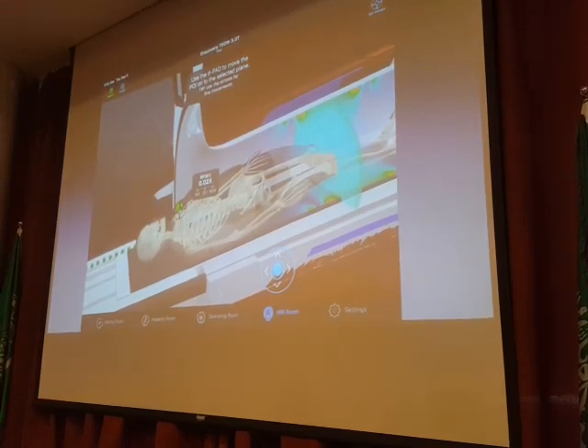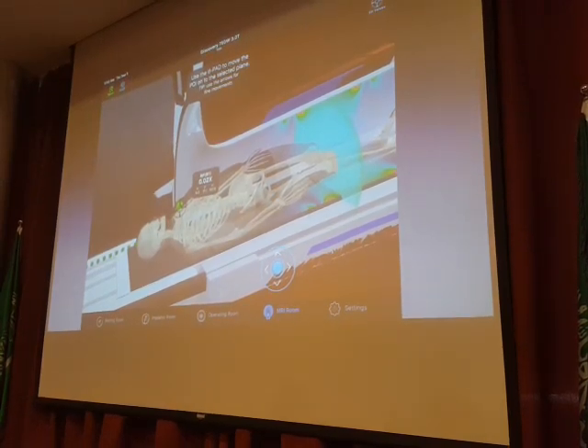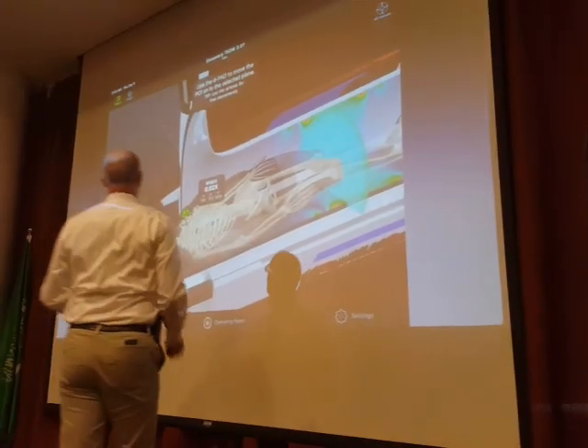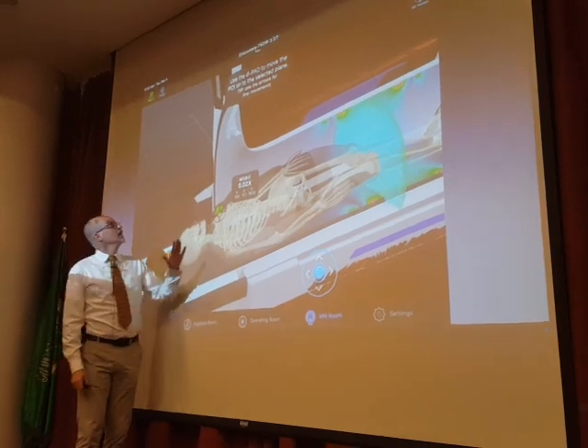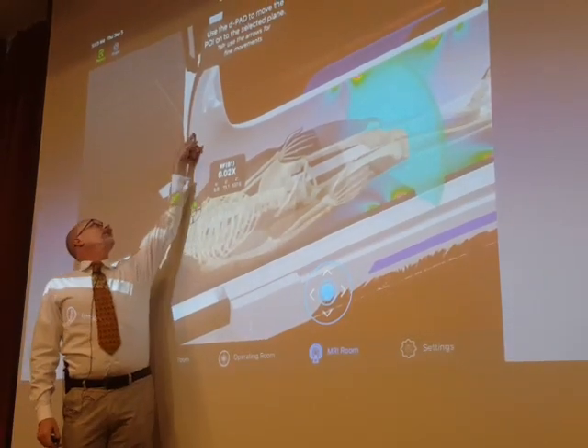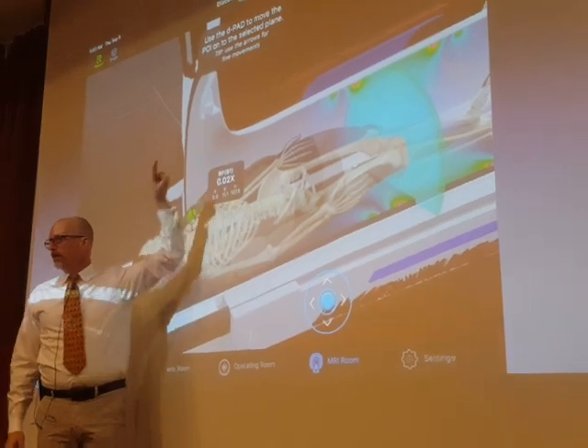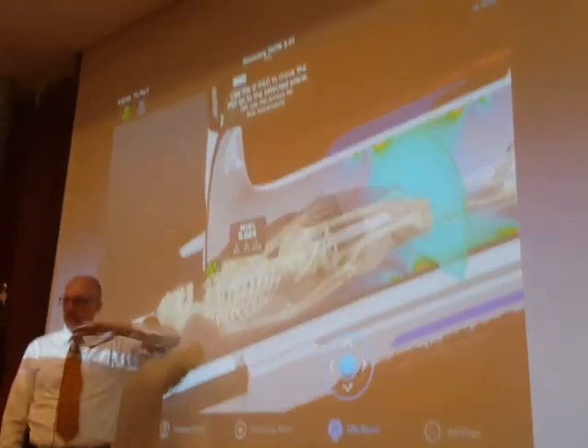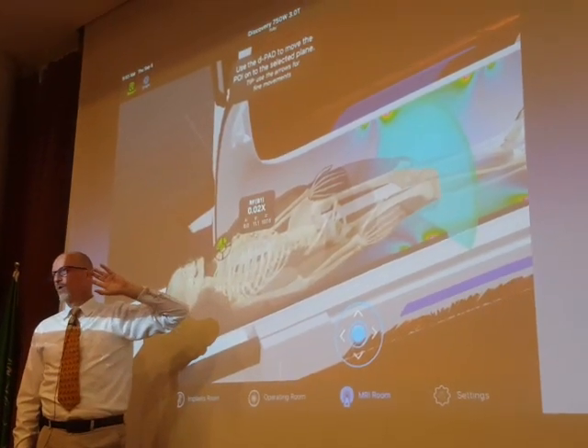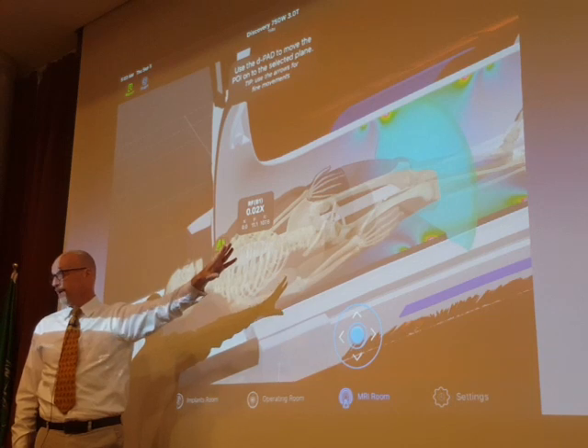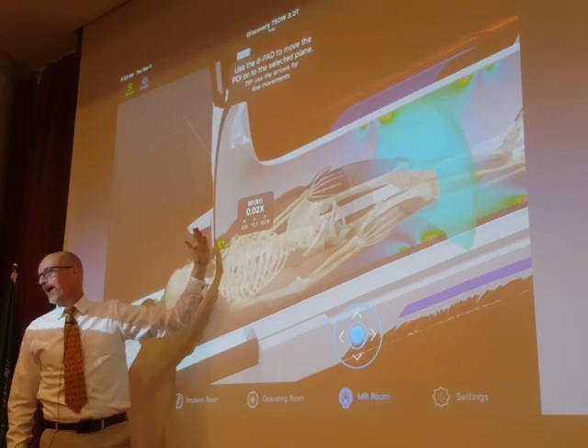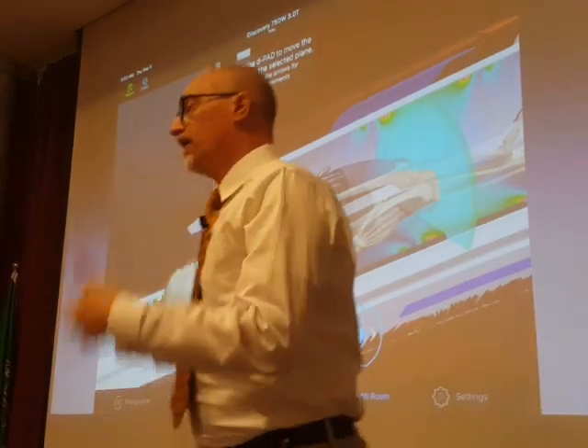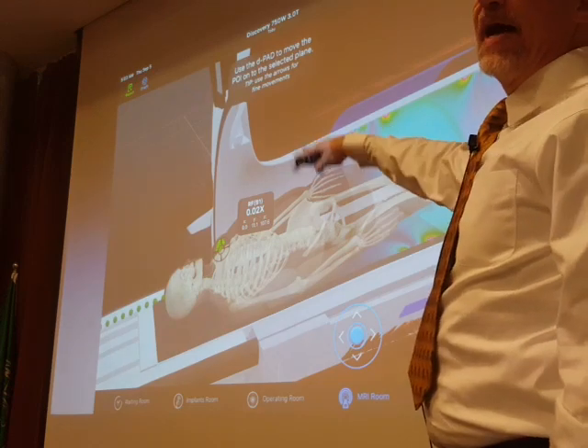You can't really make broad generalizations about what a specific value would be. My rule of thumb is if we're at the mouth of the bore, anything from that point out is a triviality — not worth thinking about from a clinical standpoint in terms of exposure. This one is kind of right at the mouth of the bore, but you would have to look at it based on each individual magnet system.